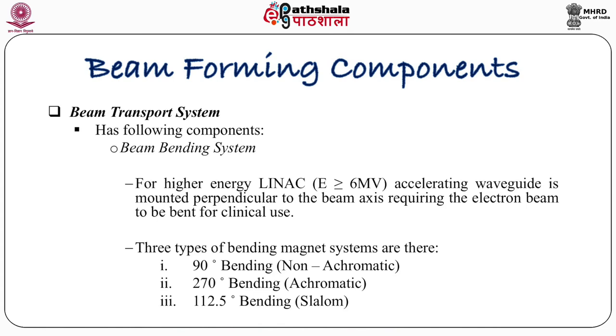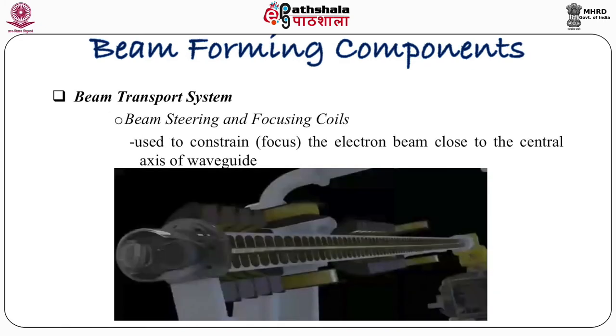The beam transport system has the following components: a beam bending system for high energy linacs where energy of the photons is more than or equivalent to 6 MV — the accelerating waveguide is mounted perpendicular to the beam axis, requiring the electron beam to be bent for clinical use. Three types of bending magnet systems are used: 90-degree bending (non-achromatic), 270-degree bending (achromatic), and 112.5-degree bending (slalom). The figure shows the waveguide, beam steering, and focusing coils used to constrain or focus the electron beam close to the central axis of the waveguide.